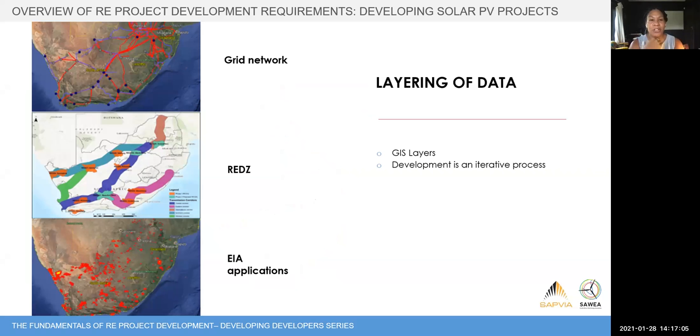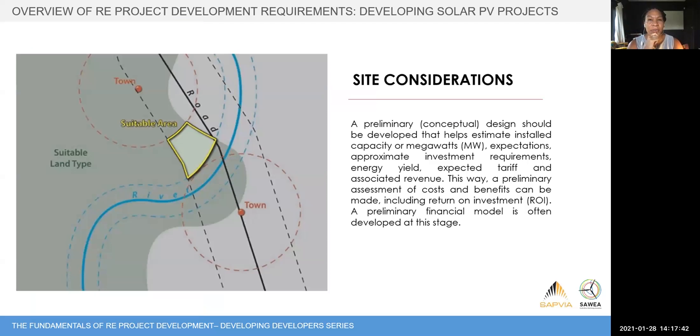Project development is iterative — you don't just suddenly pick a site. You go through different processes looking at different criteria. You can look at site factors on a country-wide basis using GIS: the grid network, the REDZ, EIA applications, and competition. Putting all of those together helps you find available areas that are most competitive. After going through your various iterations, you're left with a suitable area — marked in yellow — which tells you the available capacity in megawatts you can build and helps you understand potential return on investment based on size, revenue, and project costs.